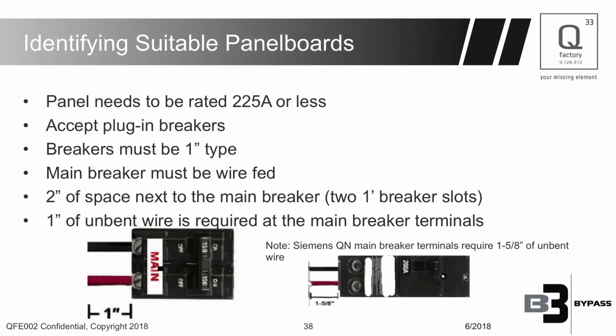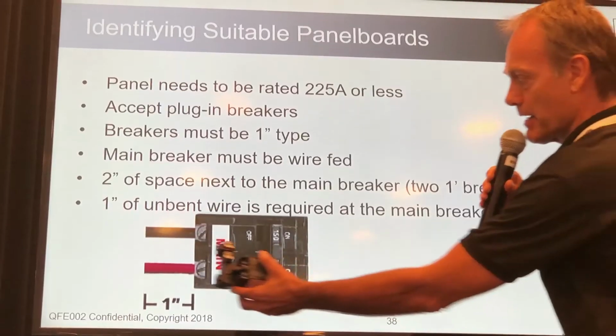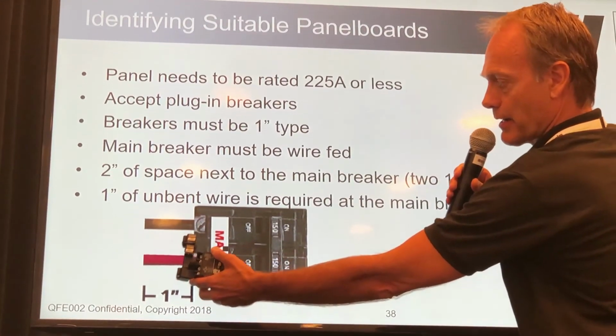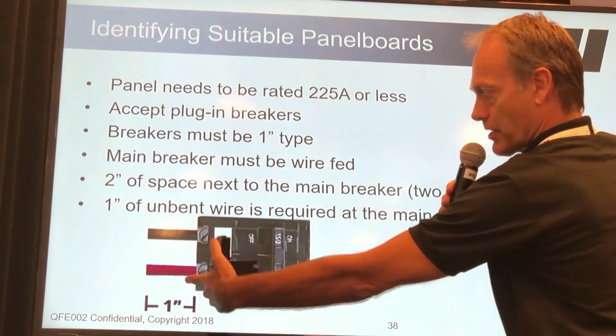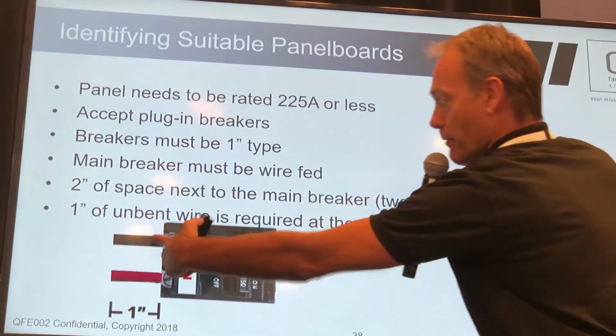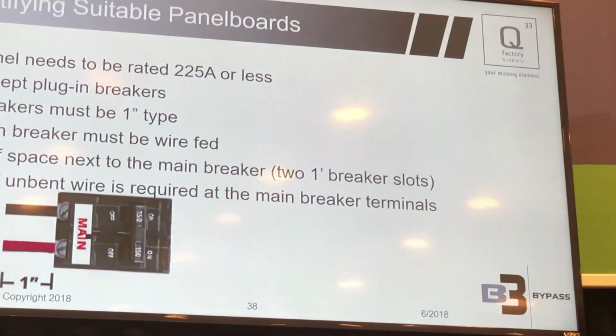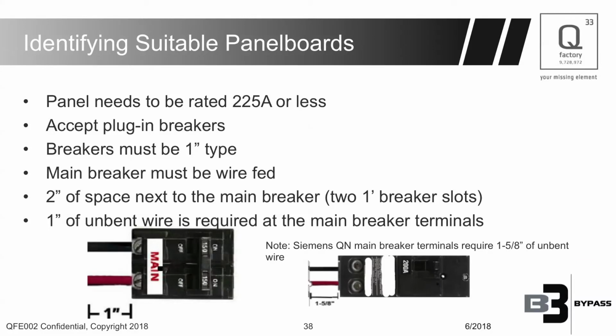The main breaker should be wire fed. We're working on some possible adapters for busbar fed mains, but today it needs to be wire fed. And then typically we need at least 1 inch of unbent wire so we can attach to it. So if this is the existing main, the B3 will be right here and will attach to the feeder wires of the main before they enter the main breaker. So basically we're connecting between the meter socket and the main breaker.